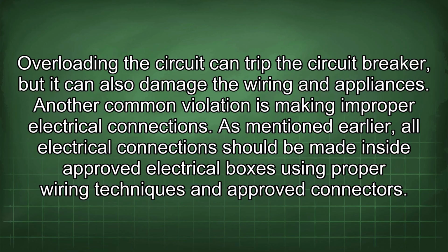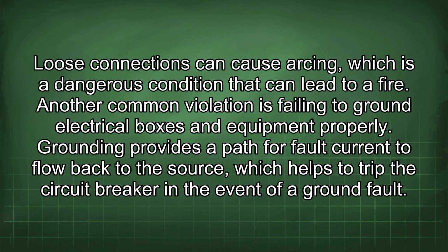Another common violation is making improper electrical connections. As mentioned earlier, all electrical connections should be made inside approved electrical boxes using proper wiring techniques and approved connectors. Loose connections can cause arcing, which is a dangerous condition that can lead to a fire. Another common violation is failing to ground electrical boxes and equipment properly. Grounding provides a path for fault current to flow back to the source, which helps to trip the circuit breaker in the event of a ground fault.